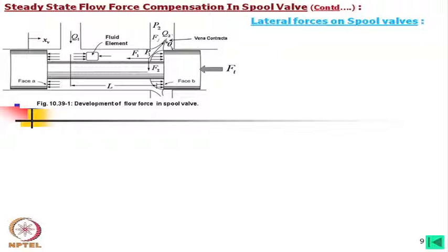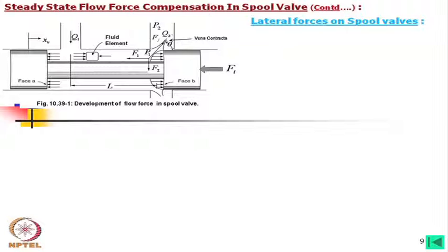Apart from the axial flow force, there is also a lateral force on the spool valve. The total jet force has two components: F1 is the axial flow force which must be controlled by the drive, and F2 is the lateral force. For a full rectangular port or uniformly distributed discrete ports, F2 forces are ideally equal and opposite around the circumference, cancelling each other.